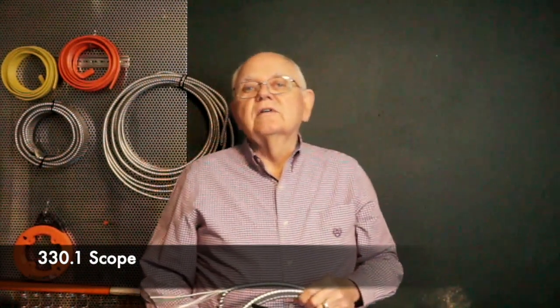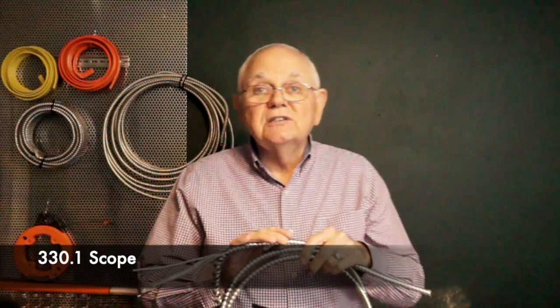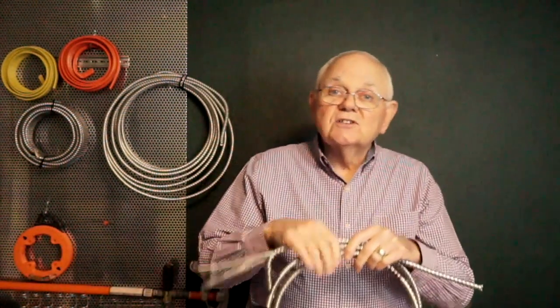We're going to start by looking at 330.1. Oh, and by the way, as we go through this Article 330, it's laid out just like all of the other cable and raceway articles. 330.1 is the scope. .2 is definitions. .10 is uses permitted. .12 is uses not permitted. .30 is securing and support requirements and so forth. So anyway, 330.1 gives us the scope for Article 330. And it says it covers the installation, the use, and the construction specifications of metal-clad cable.